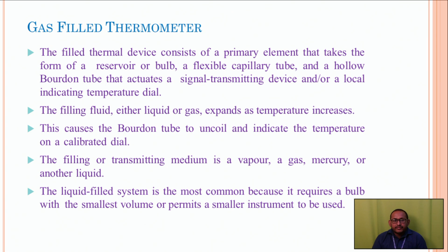Here the filling fluid, either liquid or gas, expands as the temperature increases. This causes the Bourdon tube to uncoil and indicate the temperature on a calibrated dial.